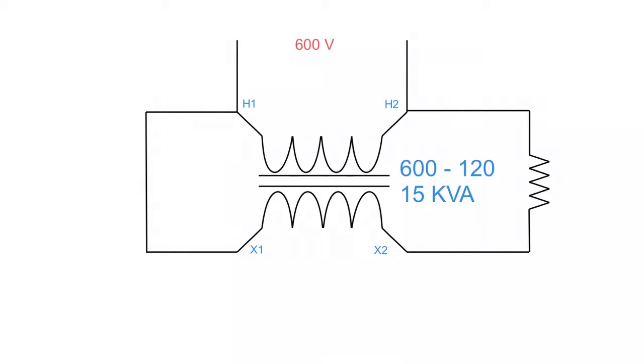In this video we're going to be going over buck boost auto transformers. An auto transformer is a transformer that shares a common winding. The difference between this type and a typical auto transformer is that here we're using a standard dual winding transformer, with the H winding on one side and the X winding on the other. We've taken a jumper and connected H1 to X1, then connected a load from X2 to H2, turning a dual winding transformer into an auto transformer through a shared electrical connection.